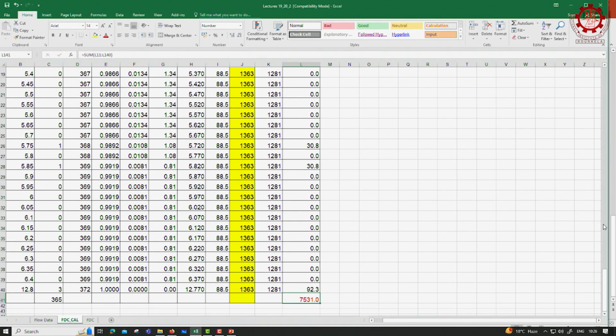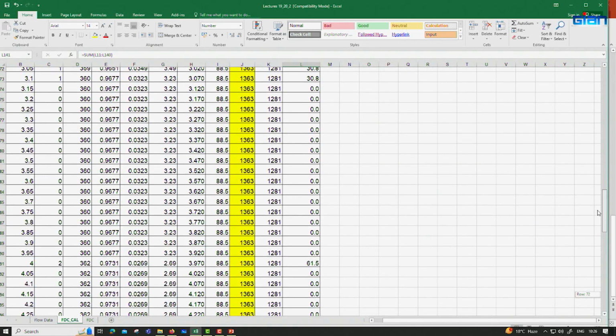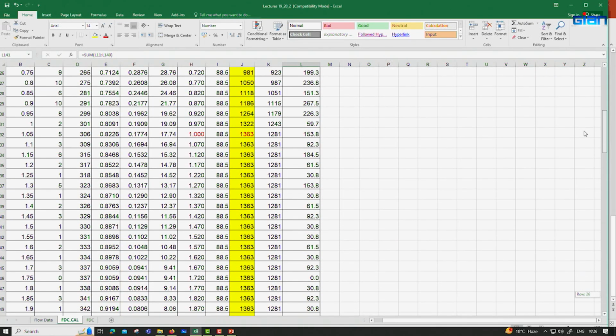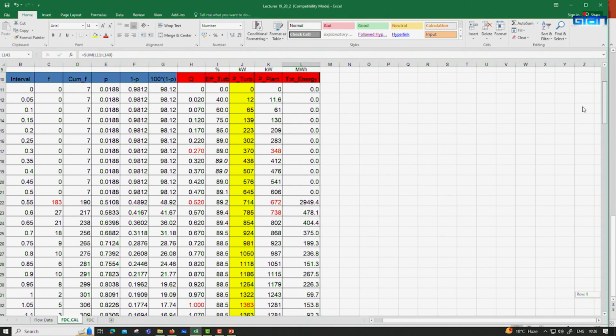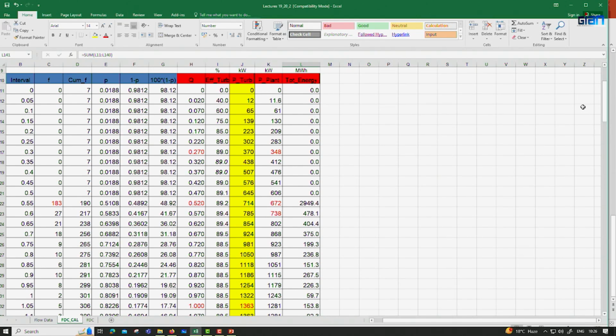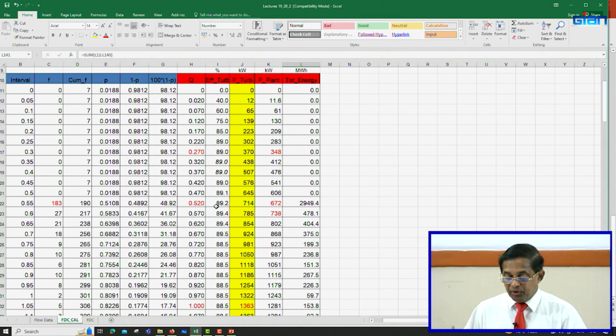See whether you have any questions, you can digest it. What I am going to show you is this same sheet can be used for a variety of calculations, different combinations of the machines. Only thing is you have to sensibly put the efficiency values, so that you can get the advantage of higher efficiencies for small rated machines, small capacity machines.